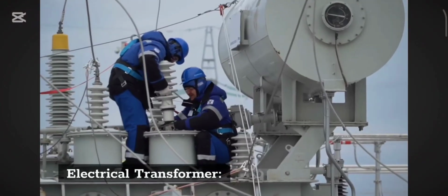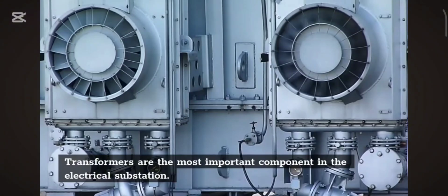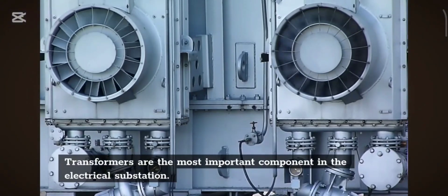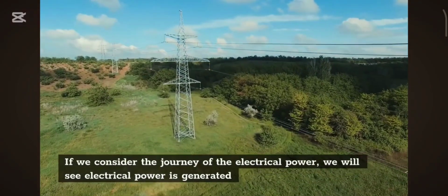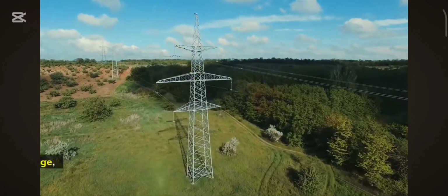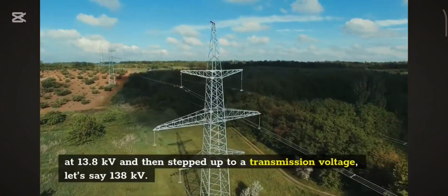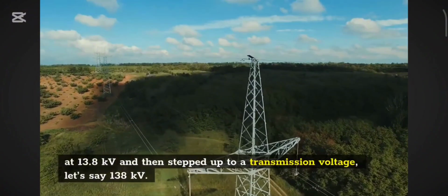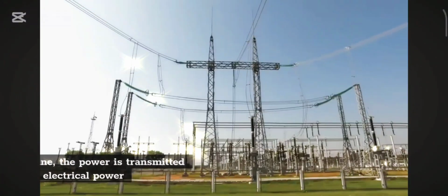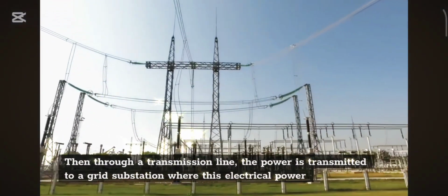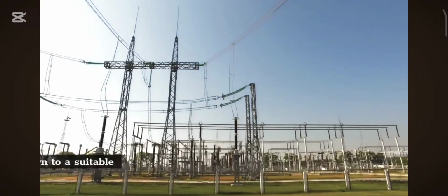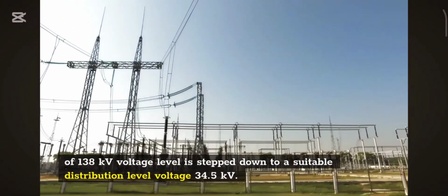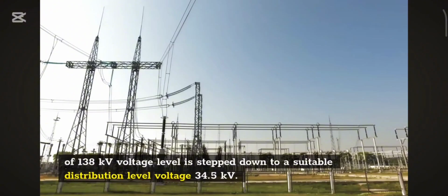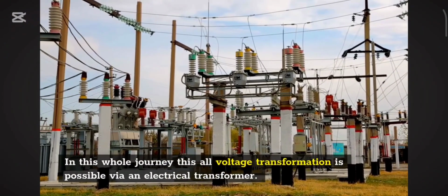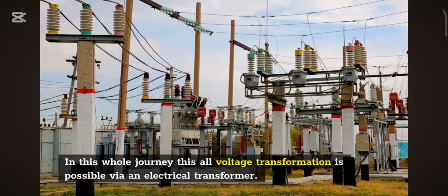Electrical transformer. Transformers are the most important component in the electrical substation. If we consider the journey of the electrical power, we will see electrical power is generated at 13.8 kV and then stepped up to a transmission voltage, let's say 138 kV. Then through a transmission line, the power is transmitted to a grid substation where this electrical power of 138 kV voltage level is stepped down to a suitable distribution level voltage, 34.5 kV. In this whole journey, all voltage transformation is possible via an electrical transformer.